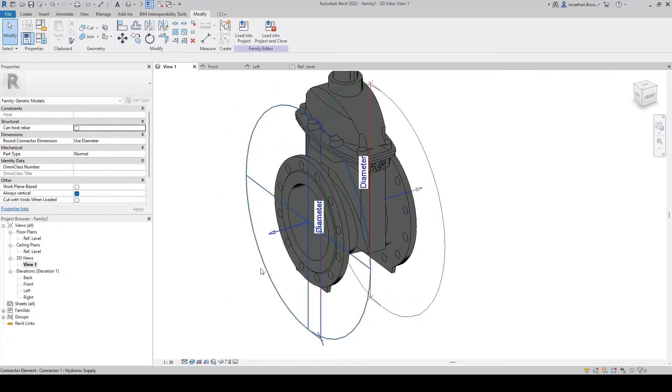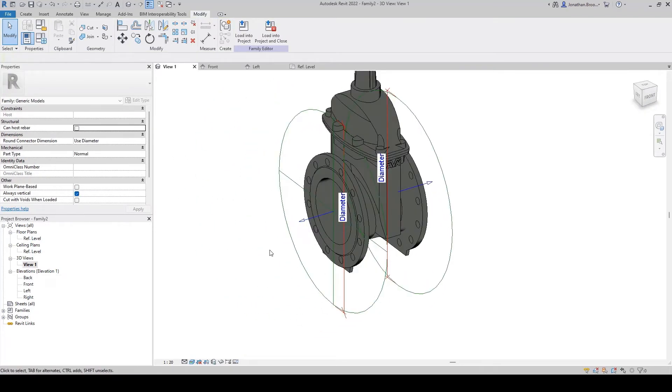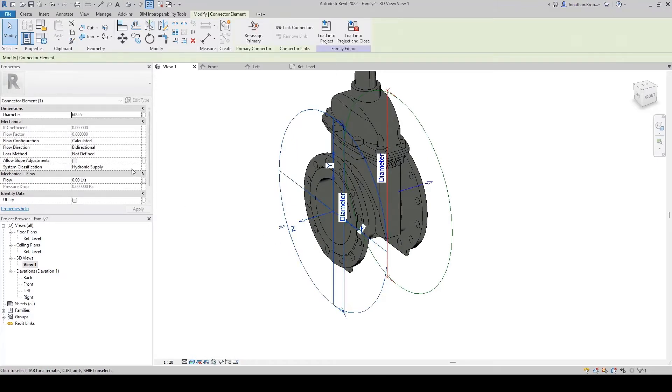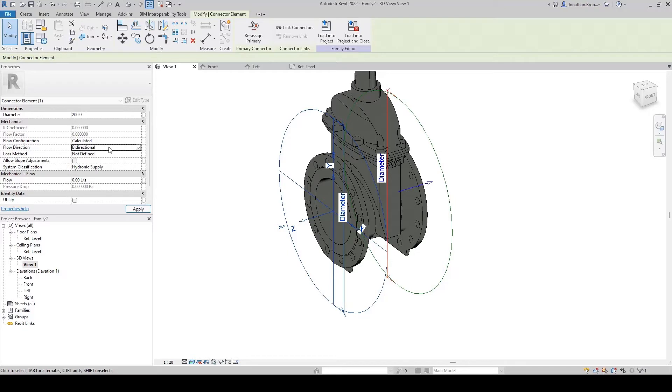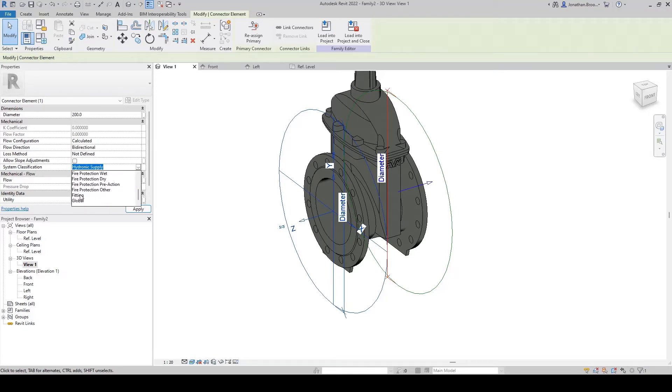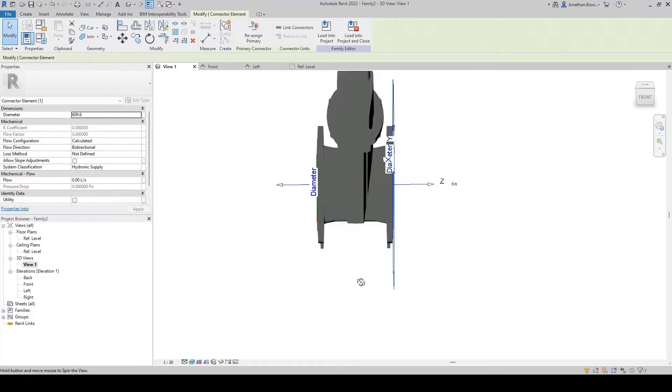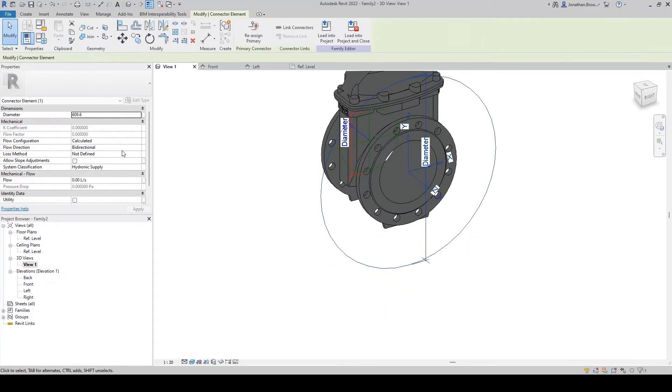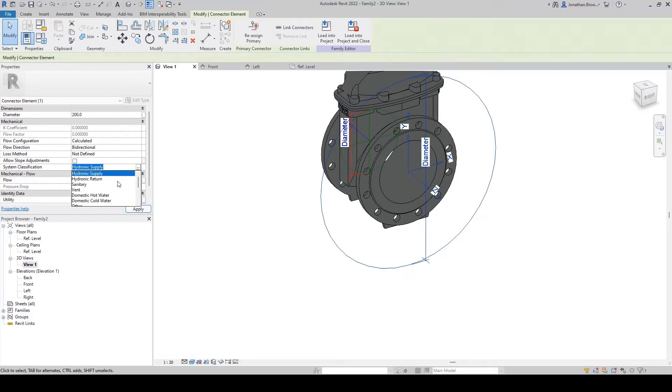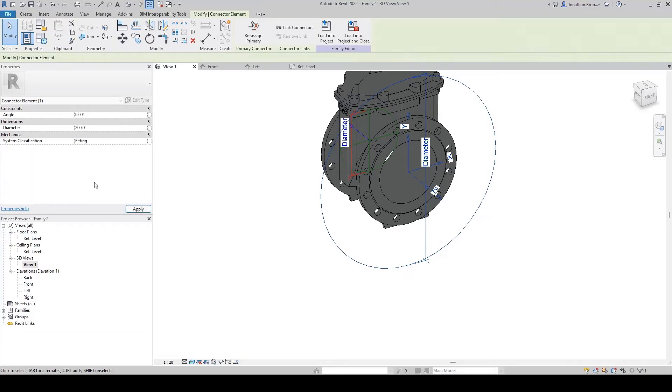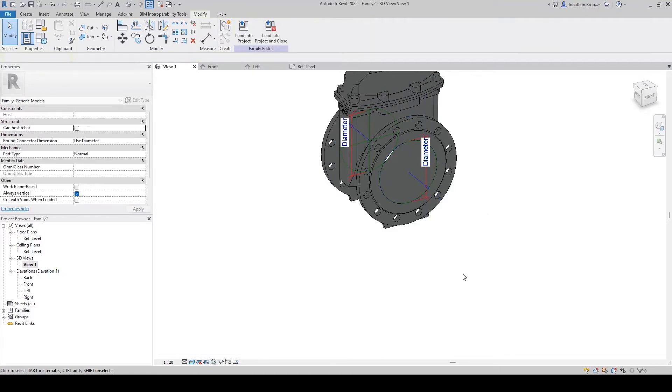Finally, we need to make sure our connection data is correct via the use of the properties pane. This allows users to add elements such as flow direction, methods for loss, system classification, and so on. In the case of our valve, we want the connections to tie into another fitting, and we're going to assign a diameter of 200 millimeters to each connection point.